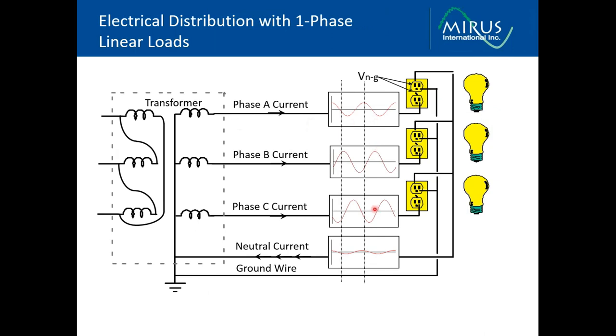When we had linear loads, such as an incandescent light bulb, and we shared a neutral with three phases, the currents flowing on each phase would end up canceling in the neutral. So you can see at this particular point in time, there was a slight negative current on phase A, positive current on phase B, negative current on phase C, so there was a resultant residual current flowing back on the neutral. Similar at this point, positive on A, negative on B, negative on C. So we're always going to have less current. The worst case scenario is the same current in the neutral as we have in the phase conductors.